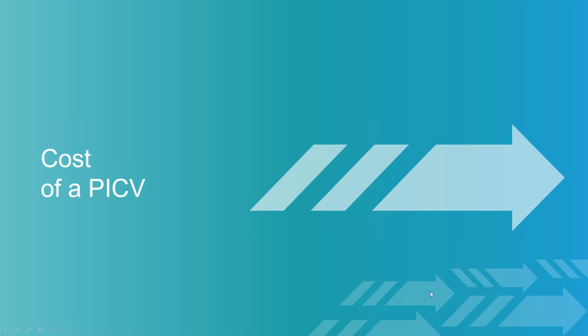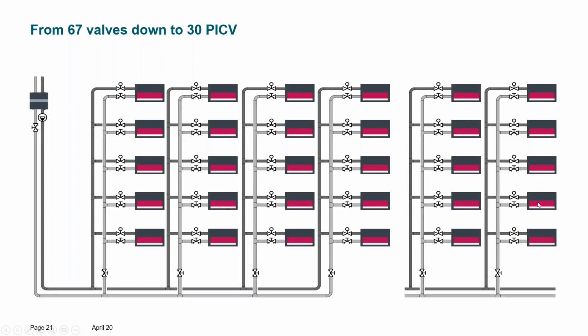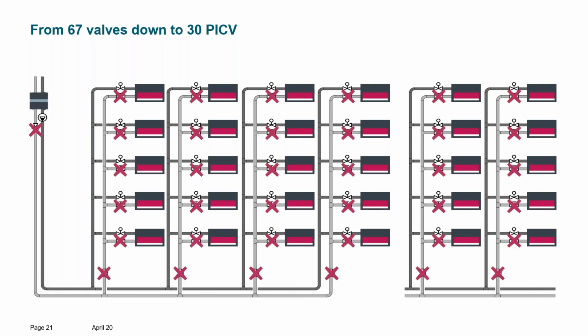And for many of you that are familiar with PICV designs, it is obvious that there is no longer a need for manual balancing valves, because a PICV is three valves in one, as you said before. And therefore, you can eliminate any other control or balancing element. But not only that. In fact, it is clearly much easier to balance a new or refurbished system, as there is no painful iteration along the coils of the whole building.